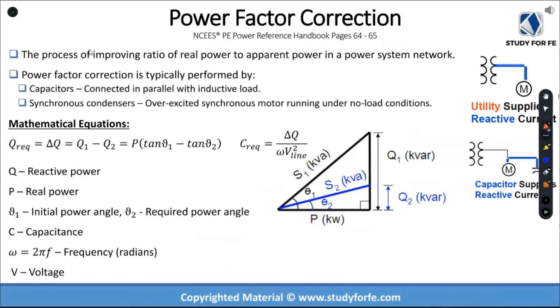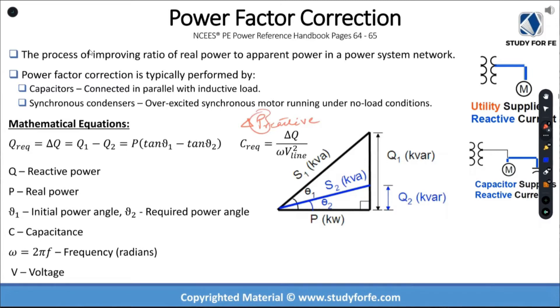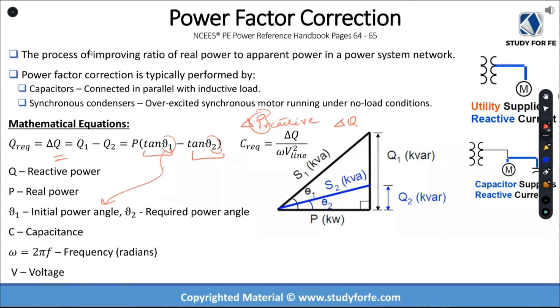Let me go over these formulas. In the handbook, on page 66 at the bottom, they use the term 'delta P reactive,' which I find very confusing because P, 95% of the time in all the textbooks, is associated with real power — not reactive. I think they should simply change that to delta Q. You can use that formula directly, but you have to make sure you're identifying these angles properly. Theta one is your initial power angle — that's your poor or incorrect power factor angle.